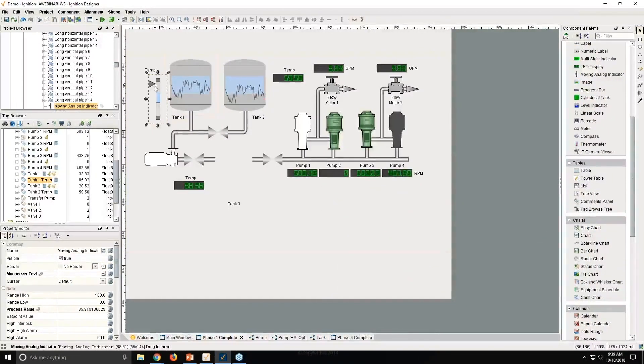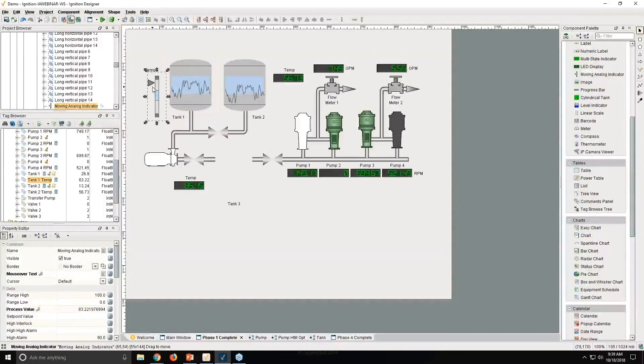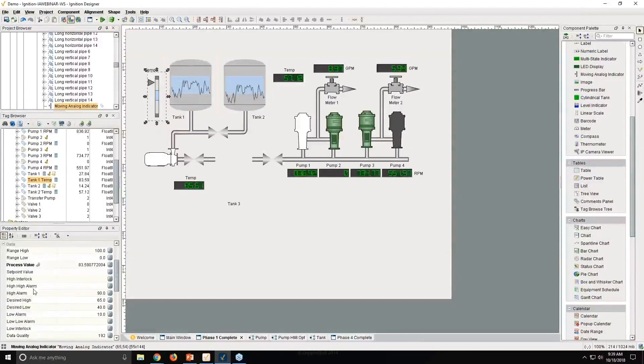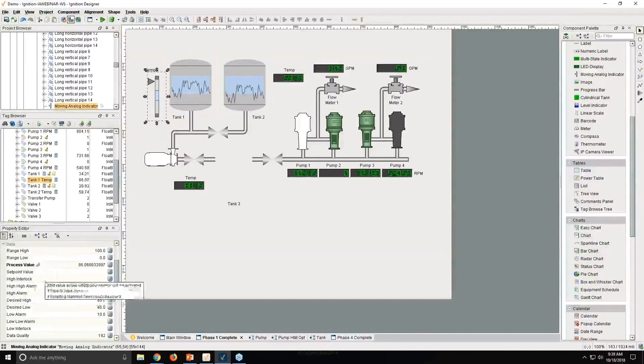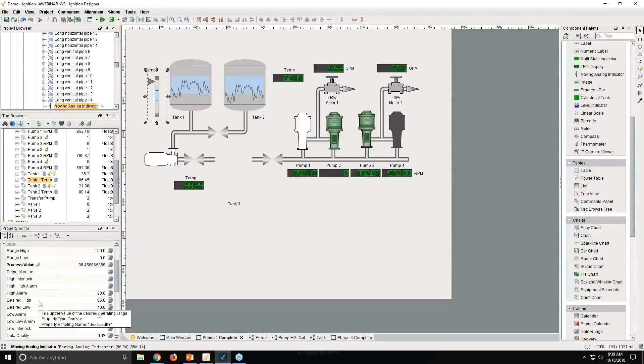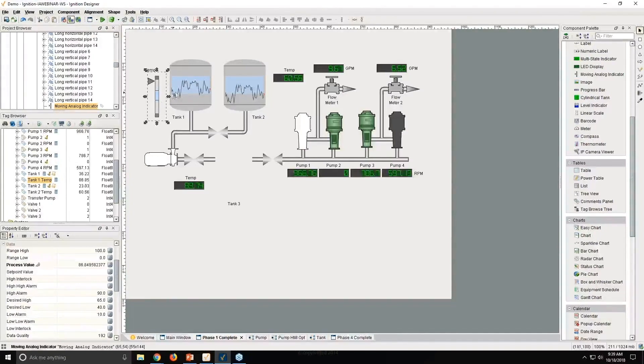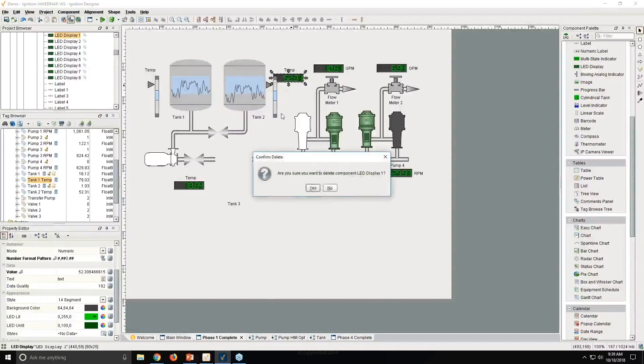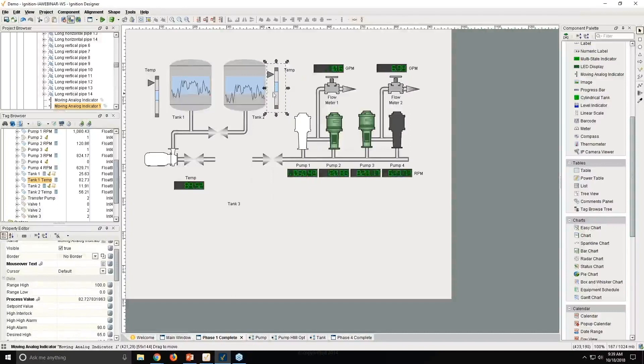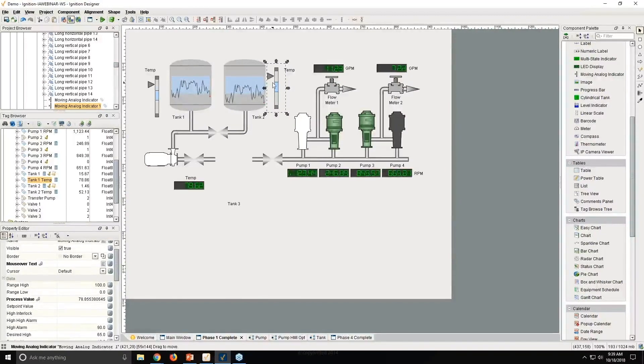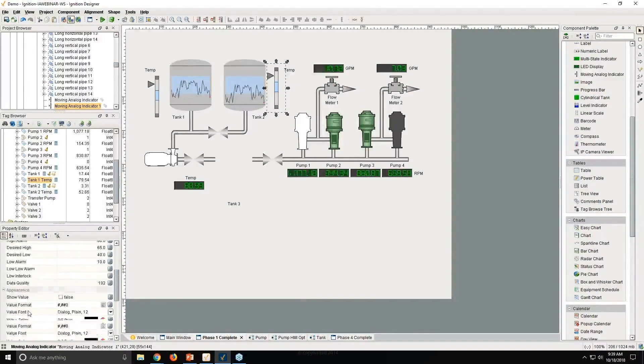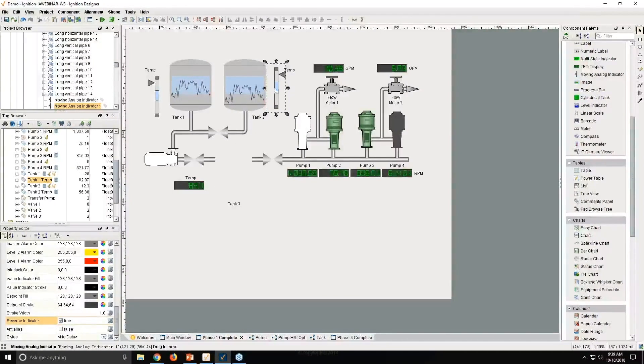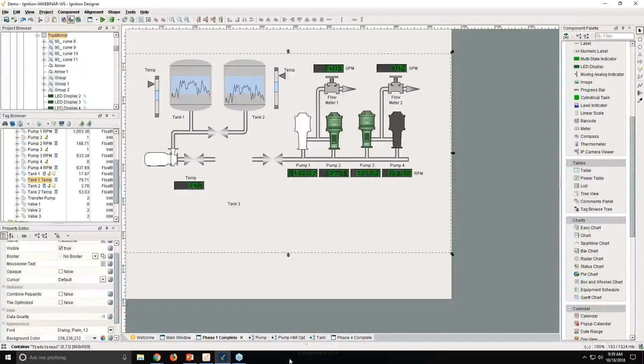It's actually showing me not just where the value of the temperature is, but it's showing me where that value is with regard to my expected value. I can come in here and set different set points where I should be in an alarm state, where my desired high and low are. And then that arrow will always show related to where my value should be. I could pull this over here. Of course, with these properties, you can change values, but you can also change how they render. You'll notice my little indicator arrow here is on the left-hand side. If I want it to be on the right-hand side for this tank two, there's a property for that as well to reverse indicator.